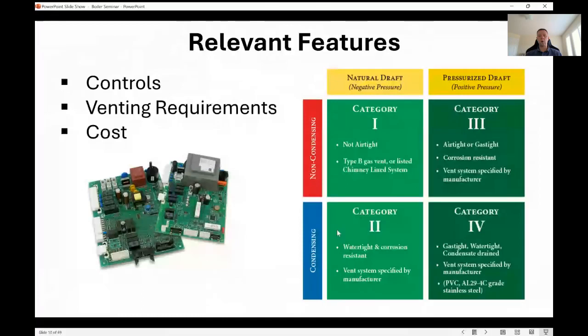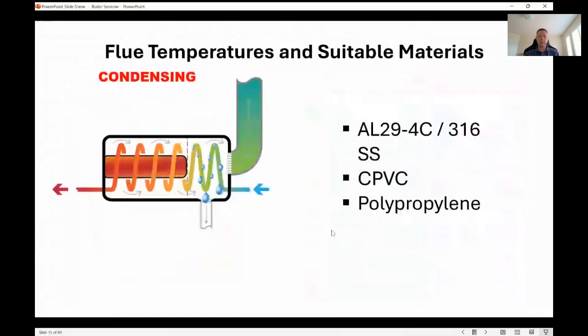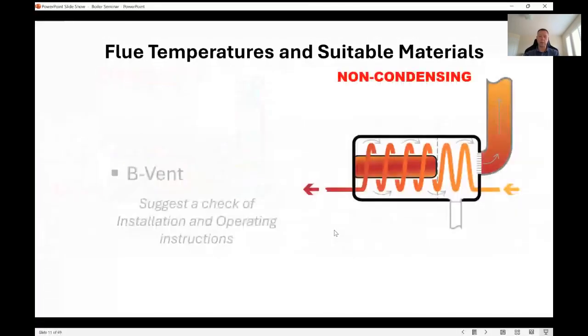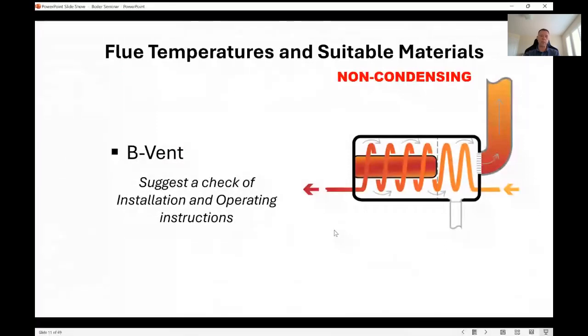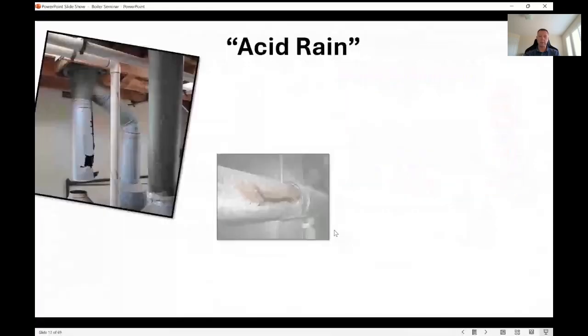Anytime you're in condensing mode, it will be a category 2 or a category 4. You're going to need a stack that can handle condensate so it doesn't rot out. When you're in non-condensing mode, it's going to be a category 1 or a category 3, and these types of stacks generally do not need to handle condensate because they're not designed to be in a condensing environment. As I said, most of what you see is CPVC. For stainless steel, AL29-4C is probably the prime grade you see out there. That was really the first, because it's very corrosion resistant. These days you're starting to see some 316 stainless as well. Polypropylene works well in a condensing boiler too. Type B vent is a very common one you see in a non-condensing application. There are other stacks as well, depending on whether you're positive pressure or negative.